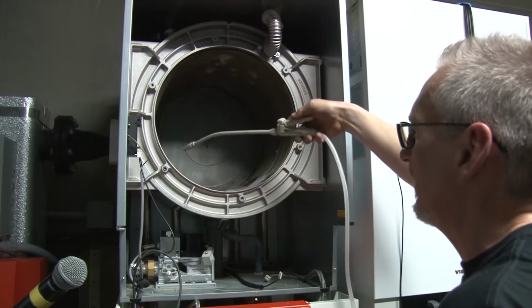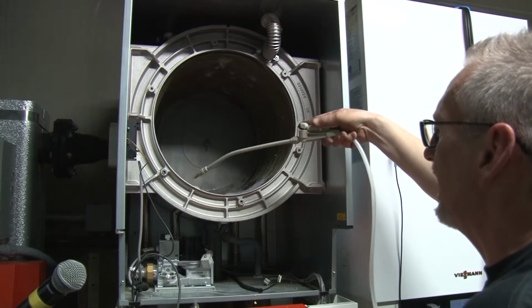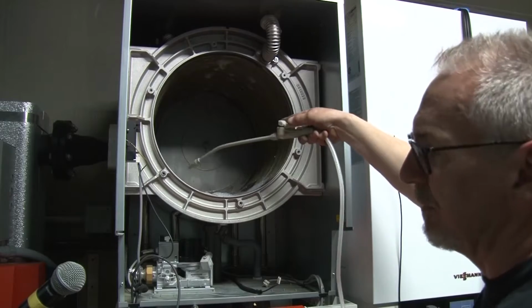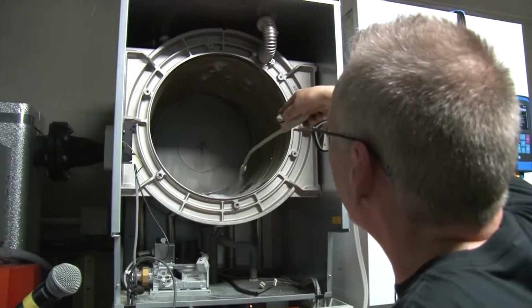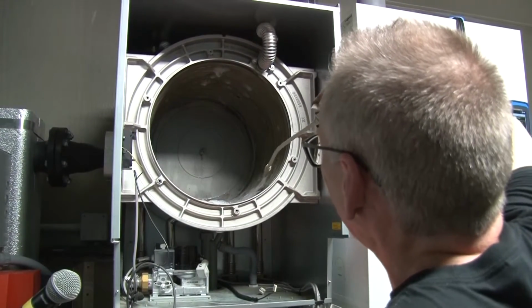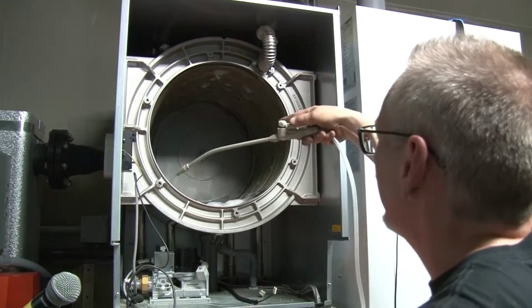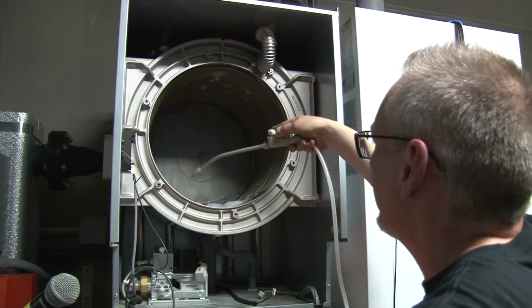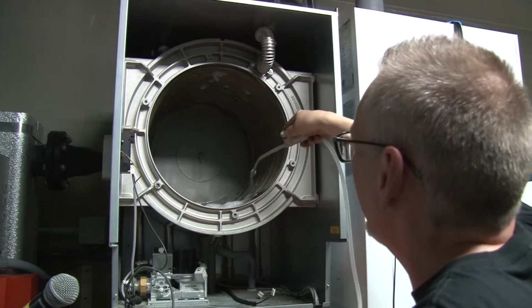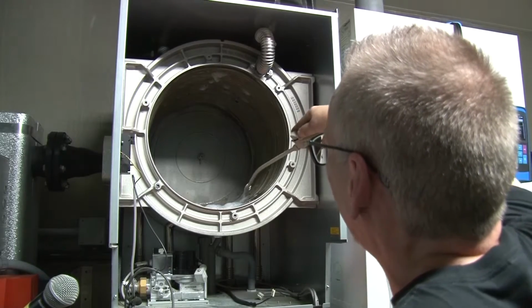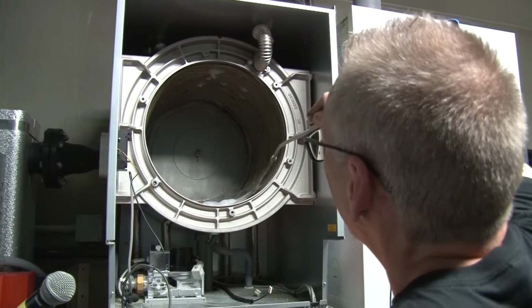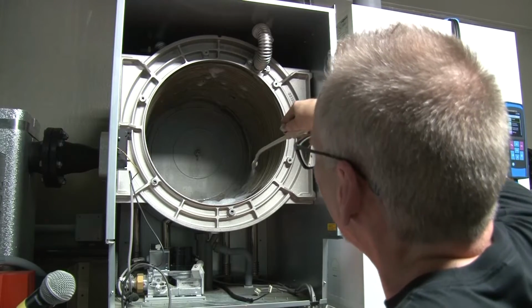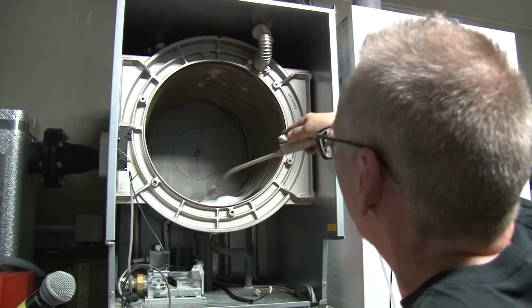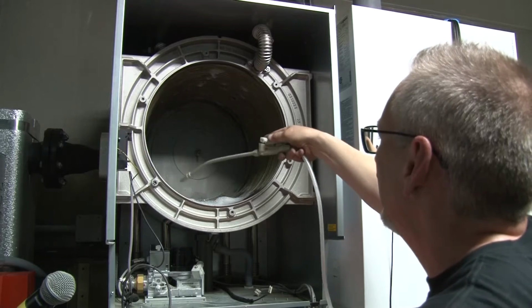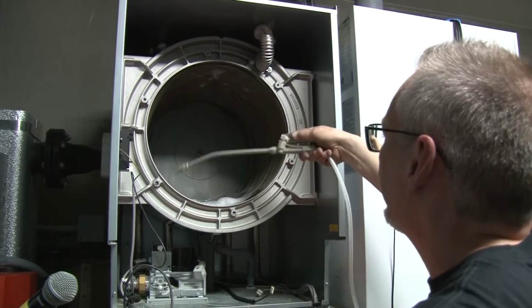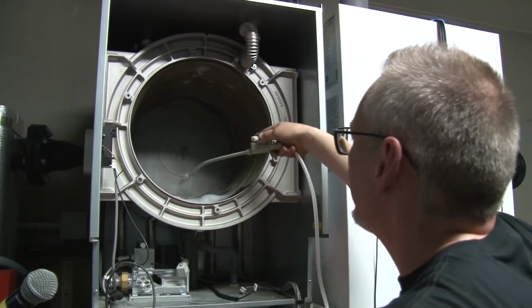And you're saturating the tube in the area that's going to have the most density of debris, kind of plugging up the heat exchanger. And you might have to do that a few times to really unplug the debris that's stuck on the heat exchanger. What happens is year after year, that stuff gets more and more compact in there and it almost becomes like a cement. And I've seen in a lot of areas where I'm from that we go to boilers and they're plugged up severely, that we've got to do a fairly decent chemical flooding like that, and it takes a few applications.